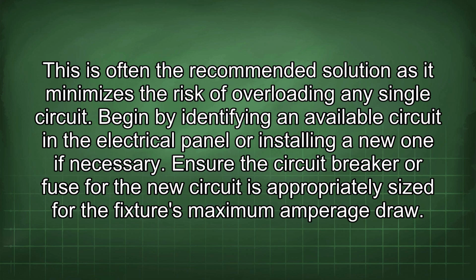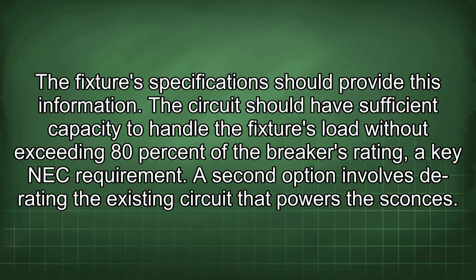Begin by identifying an available circuit in the electrical panel or installing a new one if necessary. Ensure the circuit breaker or fuse for the new circuit is appropriately sized for the fixture's maximum amperage draw. The fixture's specifications should provide this information. The circuit should have sufficient capacity to handle the fixture's load without exceeding 80% of the breaker's rating, a key NEC requirement. A second option involves derating the existing circuit that powers the sconces.